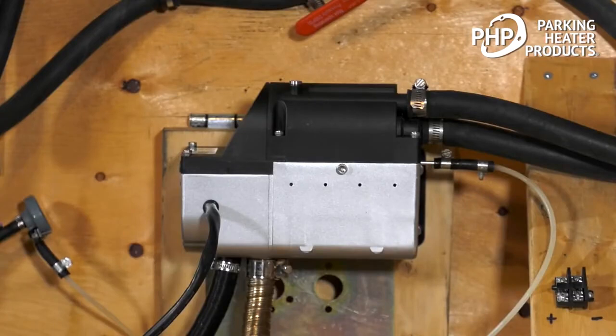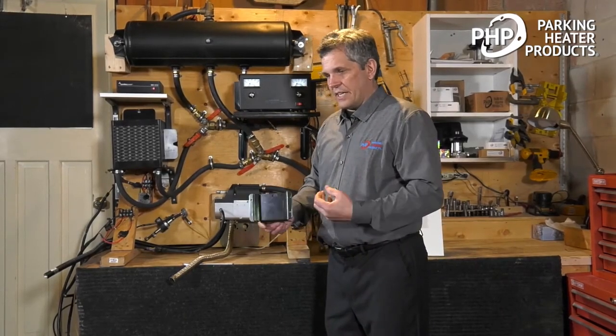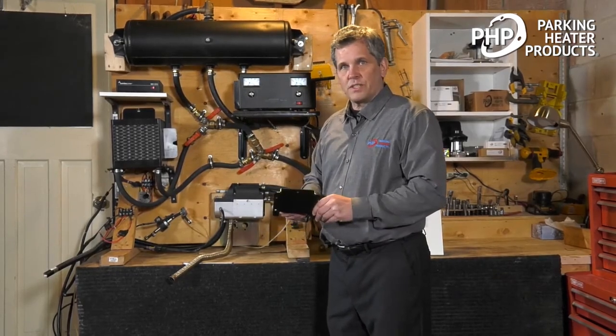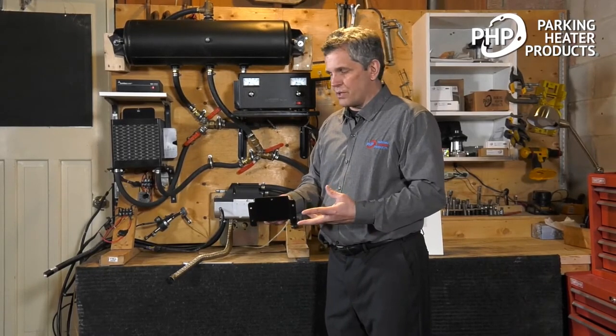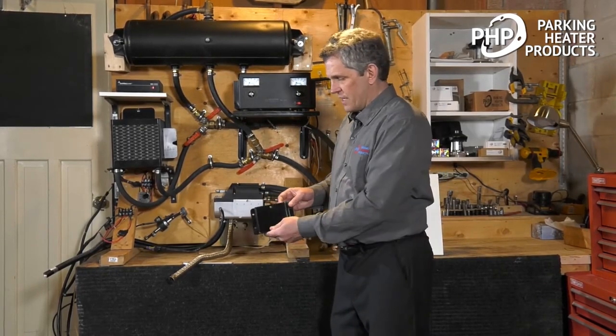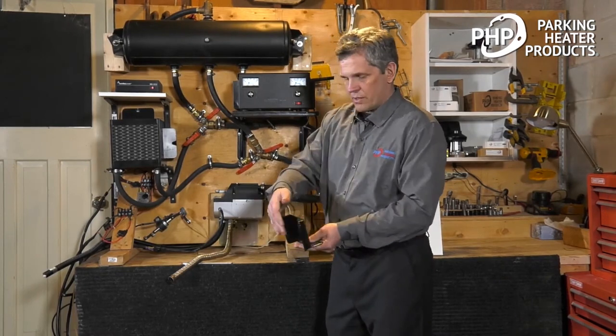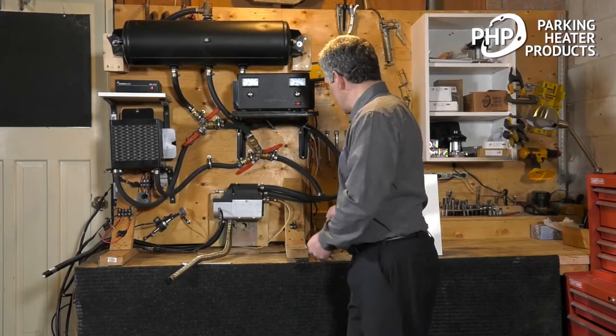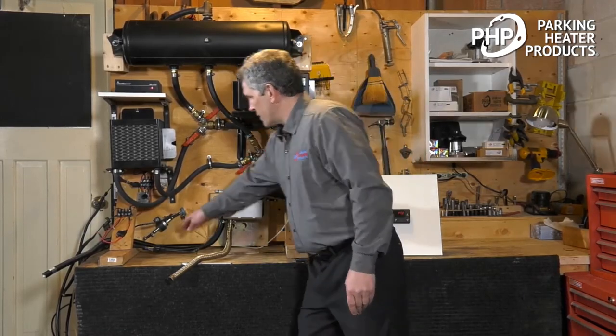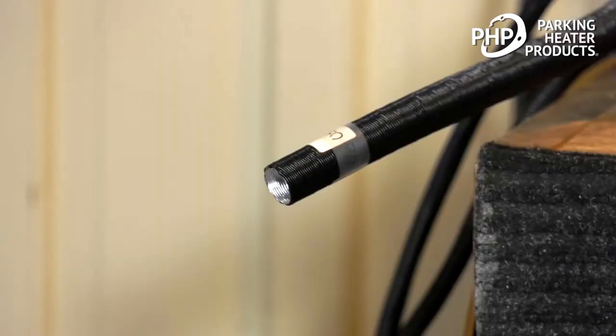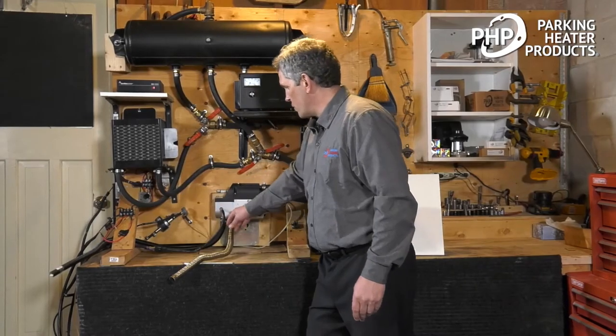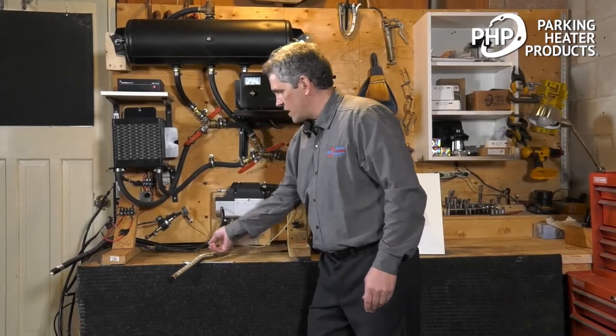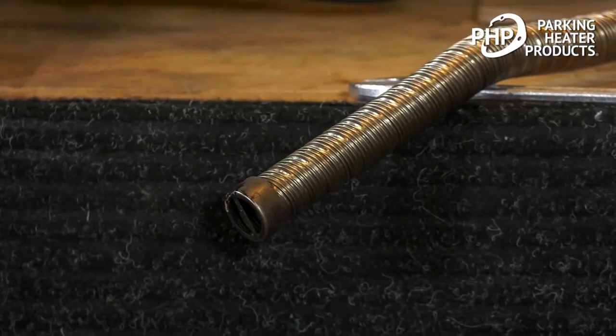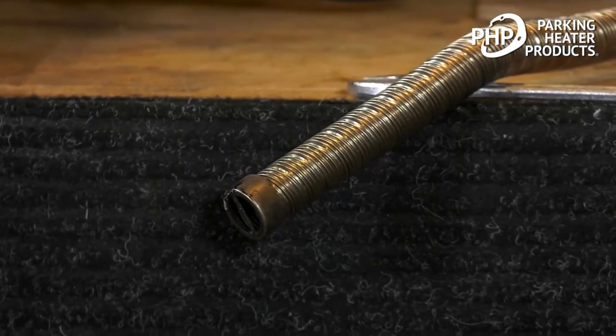The next thing we look at was how do we mount the heater. The heater is typically mounted in a splash-free zone in the truck that's reasonably well protected. We use this mounting bracket. The heater mounts directly to this, and then you can mount that to a flat surface. Combustion air intake: we take the combustion air from a clean place so it's not ingesting dust or dirt, snow. And then the exhaust. We send the exhaust to a safe place outside of the vehicle.